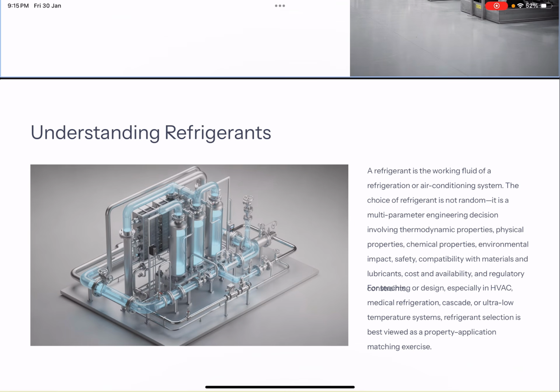So the choice of refrigerant, which refrigerant to choose, is not random. It is a multi-parameter engineering decision, and we need to consider the thermodynamic properties, the physical properties, the chemical properties, as well as the environmental properties while we select the refrigerants. Not only that, we need to be aware of the compatibility issues, especially whether the refrigerant will work with certain materials or not, how it will affect the lubricants used in the refrigeration system, as well as the regulatory aspects of the refrigerants, especially in the context of ozone depletion and global warming.